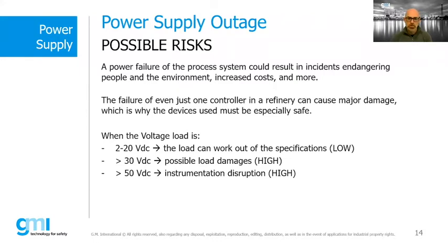But what are the dangerous conditions for a power supply system? Well, mainly there are two dangerous fault conditions. The first one is an indefinite load voltage in a range between 2 and 20 volts. This must be considered a dangerous failure of a power supply. This is because an incorrectly powered load works, or can work, out of specification, and this leads to a reduction in load performance that can cause a premature instrument failure.